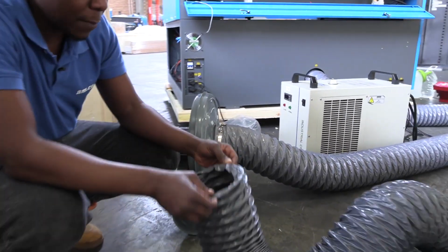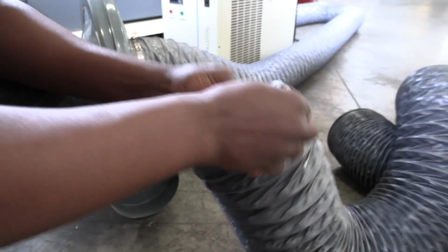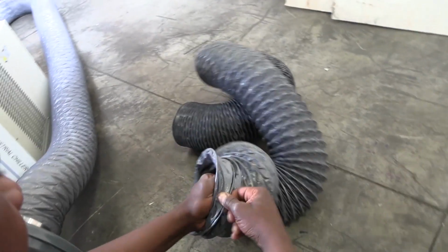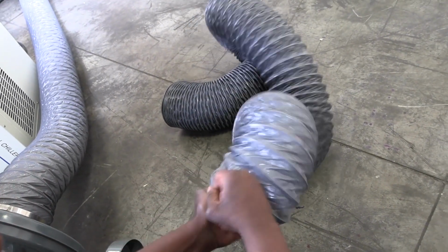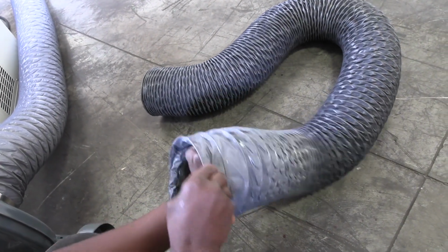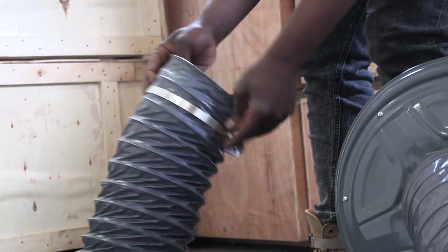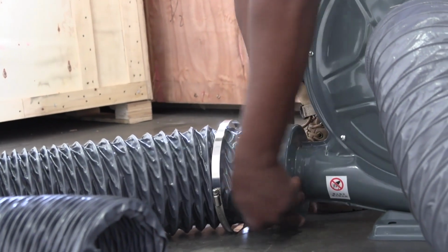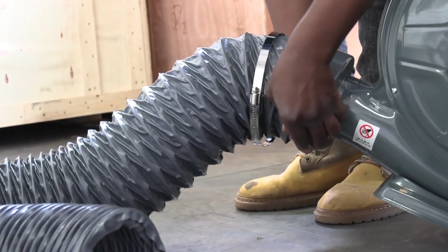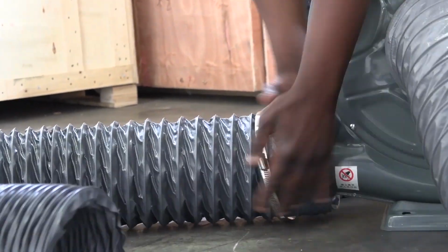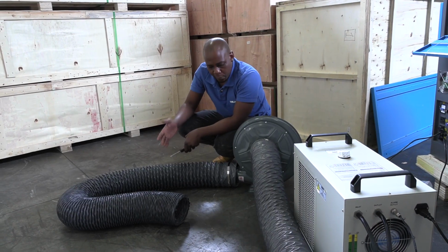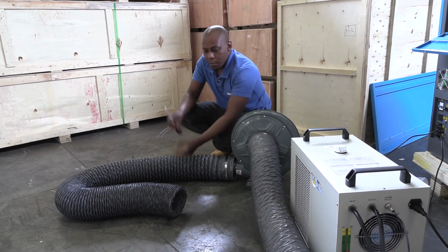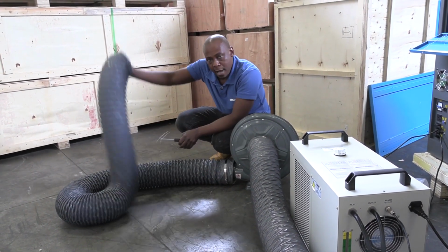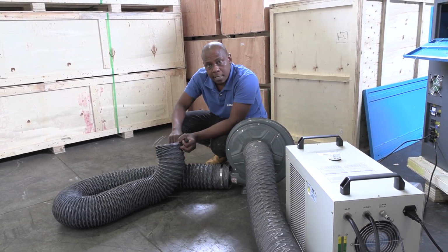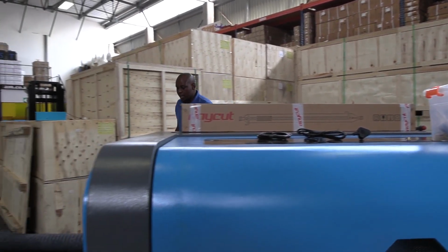Right. Same applies. I'm just going to fold in a little bit inside so that I can find a very good spot to secure my extraction hose onto the outlet of the extraction fan. Slip the clamp first and secure it onto the outlet of your extraction hose. Right, now that we have installed our exhaust fan, you can now let this side of the hose just run out through an outlet going outside. Now that's done. Let's now install our air pump.